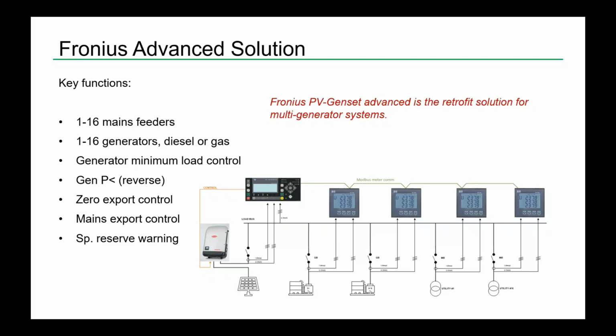Zero export control and mains power export control can be performed because we have the measurements of the mains. Here we can see that with the advanced solution, just to note, the utility incomers are summed up. So it is the sum of the export or import that is the actual set point. If you export 50 on each utility feeder, then your total export is 100 kilowatt. So if your set point is 100 kilowatt, you are in balance.